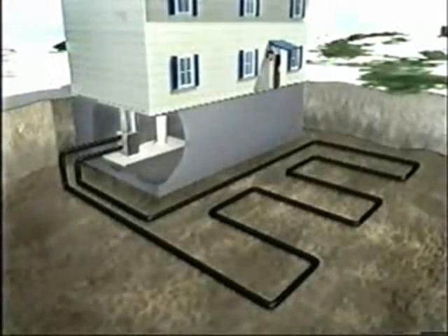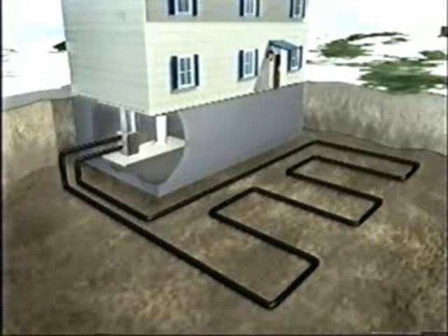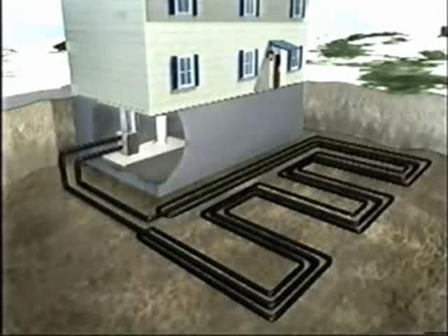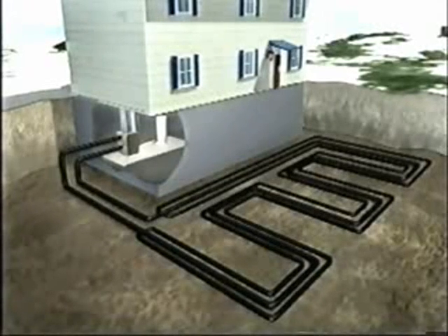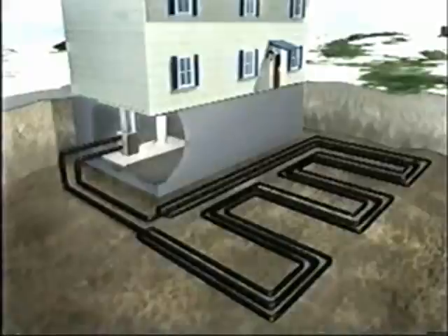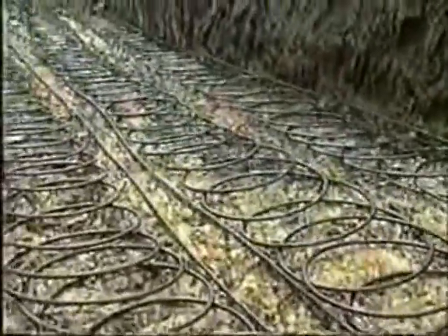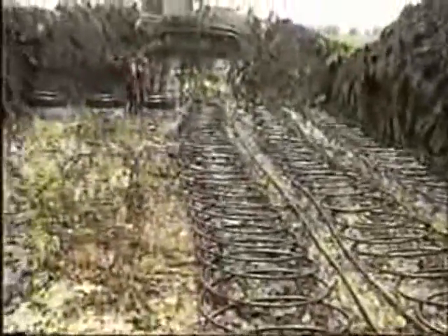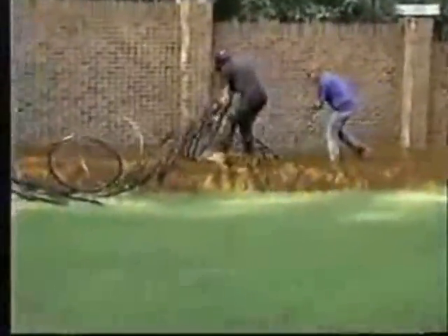In some installations, the pipes of a closed-loop system can be placed in a horizontal trench dug below the frost line. The number of pipes in each trench and the number of trenches needed will vary depending on the size of the GeoExchange system being installed and the type of soil found in the area. To minimize trenching, slinky coils, spring-like coils of polyethylene pipe, can often be used to increase the pipe surface area and thus the heat exchange per foot of trench.